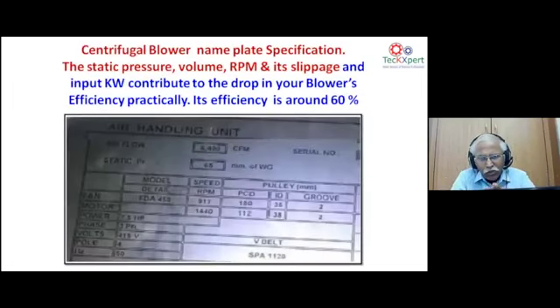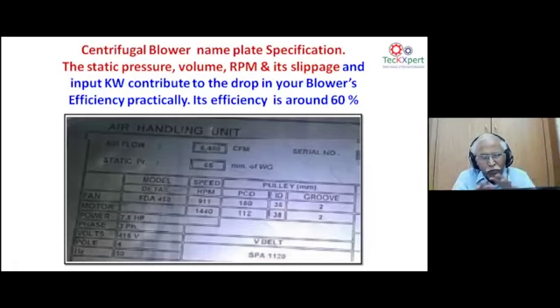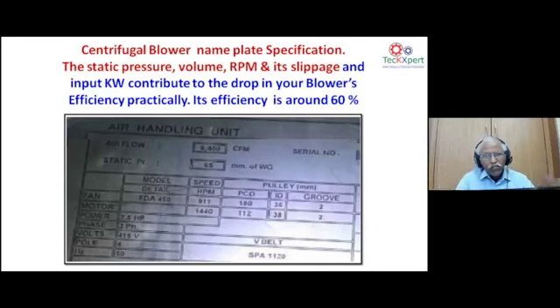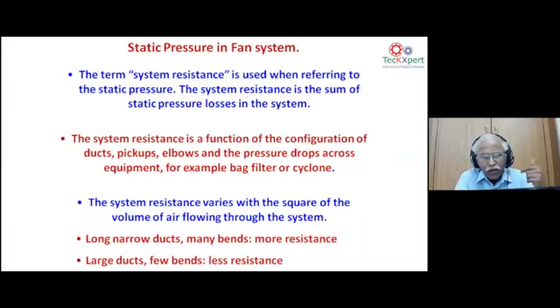Check what the blower nameplate specifies: static pressure, volume, and RPM. In AHUs in many buildings audited, almost 20% belt slippage was found — neglected because the equipment is in a secluded area. IoT sensors on blower speed can monitor RPM and detect transmission losses. If a blower's efficiency is only 60%, static pressure and RPM slippage of 10–20% can be corrected with monitoring. This is a critical but often overlooked area.